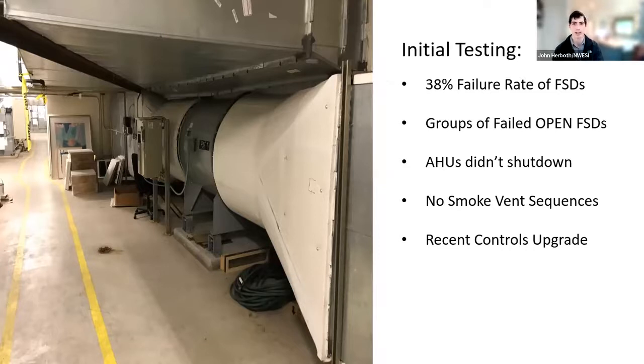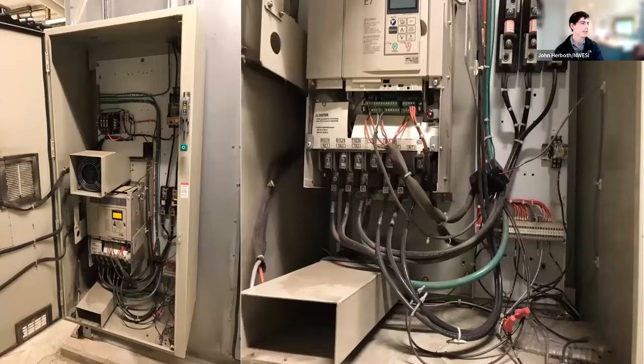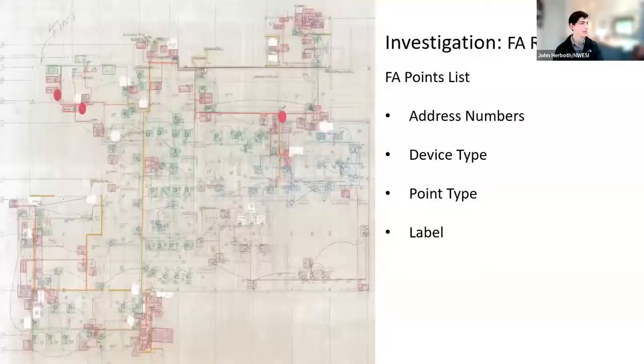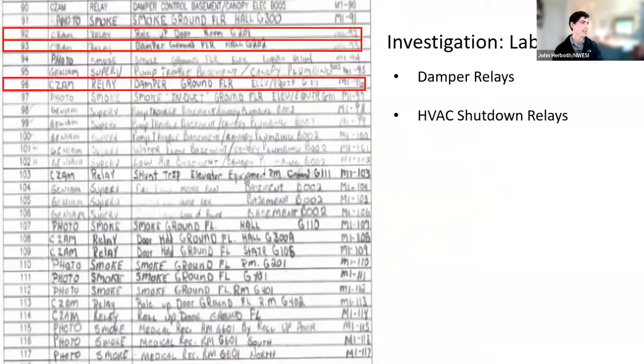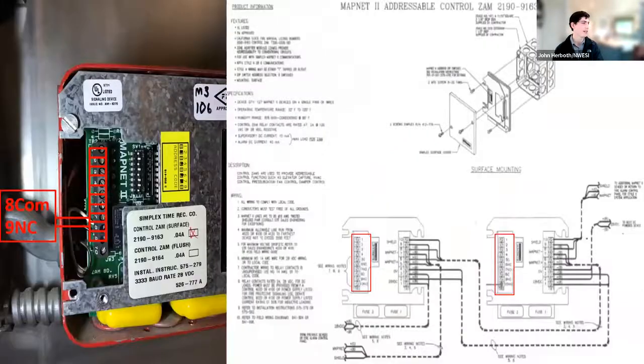They had a controls upgrade that messed with the wiring to the VFDs, which were really old. So you run into all sorts of stuff that a commissioning or TAB provider, depending on your experience, could handle. This could not be done by a mechanical, electrical, or sheet metal contractor. You need somebody that has good investigation skills, troubleshooting skills. Maybe you do have that type of contractor, who knows? Old fire alarm drawings, fun, old relay descriptions in handwriting, so that you could go track everything down.